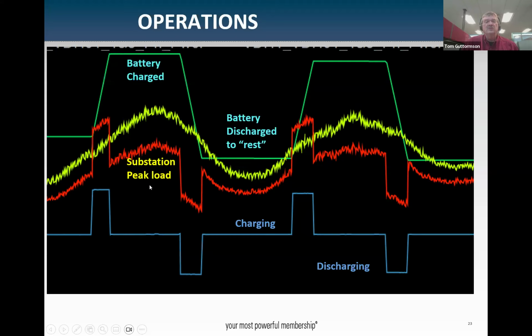So what we're trying to do is when the sum of those two transformers equals a value that's equal to or higher than the rating of one transformer, we want to have that battery charged up and ready to go in case we need that capacity. The theory is, if we lost one of these transformers and the other had to pick it up, we don't want to overload that transformer. So that's what the battery is there for, to supplement that power need.